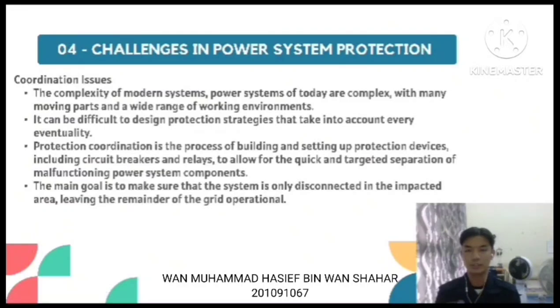Okay, next, challenges in power system protection. First, coordination issues. Modern power systems are complex, with many moving parts and a wide range of working environments. It can be difficult to design protection strategies that take into account every eventuality. Protection coordination is the process of building and setting up protection devices, including circuit breakers and relays, to allow for the quick and targeted separation of malfunctioning power system components. The main goal is to make sure that the system is only disconnected in the impacted area, leaving the remainder of the grid operational.